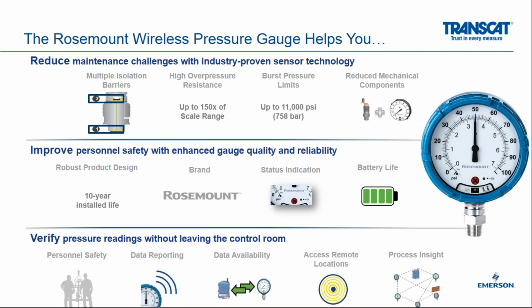It has a brand that you can trust, status indication to let you know if something's going on, and a battery life that's going to last a very long time. And then finally, you can verify those readings, not only locally, but wirelessly. You can keep personnel out of harm's way if you don't need to put them in harm's way. You can report all of that data, get all that data, compile it however you want, and access these pressure gauge readings in a way that doesn't make you walk up till you're 5 feet away from the gauge to be able to know exactly what that gauge is reading.